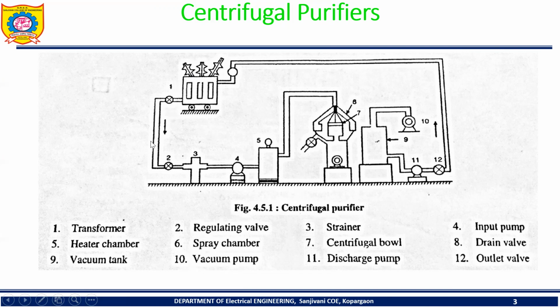Now, if you observe here, the transformer oil gets extracted from the transformer tank, through the strainer and the regulating valve. A chemical is added to purify the transformer oil, and the oil is shifted to the heating chamber by means of the input pump. Here the oil will be heated up. Why do we heat up the oil? When you heat the oil, gases and moisture are developed, so whatever gases are developed can be removed very easily. The main purpose of heating the insulating oil is to develop the gases. Whatever contaminant gases are in the oil can be developed and extracted further.